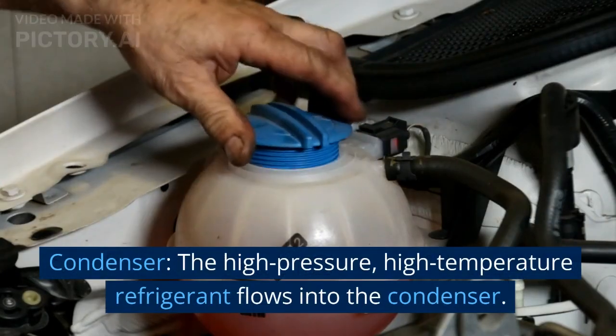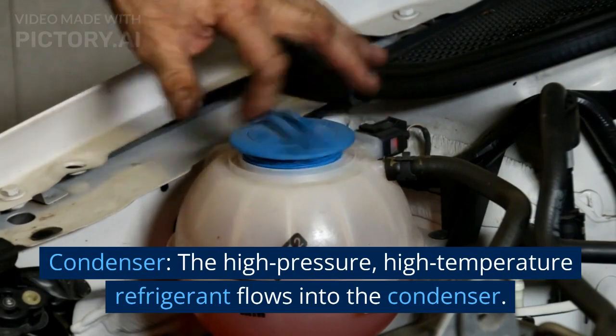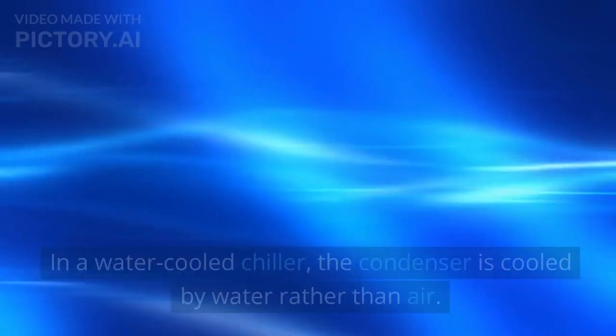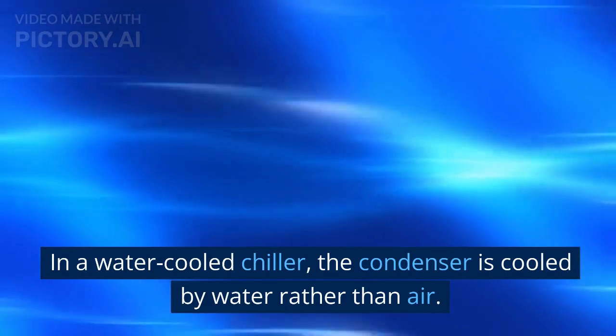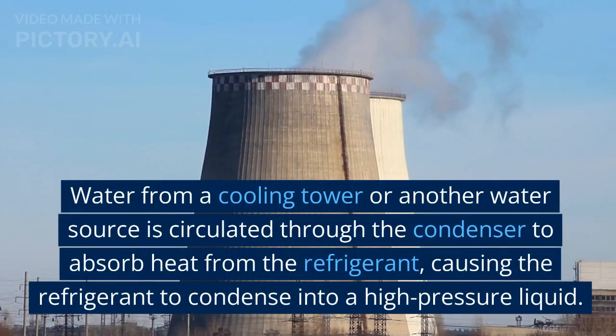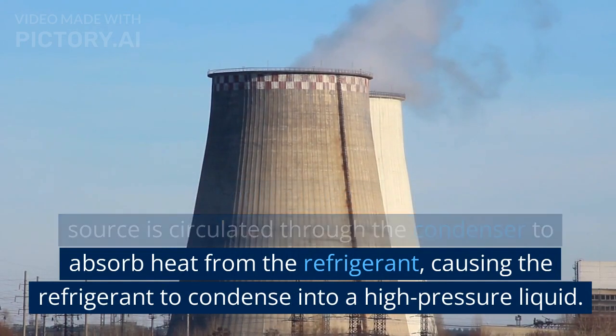Condenser. The high-pressure, high-temperature refrigerant flows into the condenser. In a water-cooled chiller, the condenser is cooled by water rather than air. Water from a cooling tower or another water source is circulated through the condenser to absorb heat from the refrigerant, causing the refrigerant to condense into a high-pressure liquid.